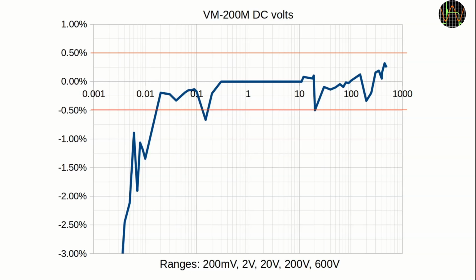DC volts accuracy is specified as ±0.5%, indicated by the red lines, and it meets this easily. The large deviation at the beginning is misleading and pretty irrelevant in reality, at those small voltages, just one least significant digit difference from the correct value creates a large error percentage. Within the most important range of 0.2 to 20 volts, the meter is amazingly accurate.